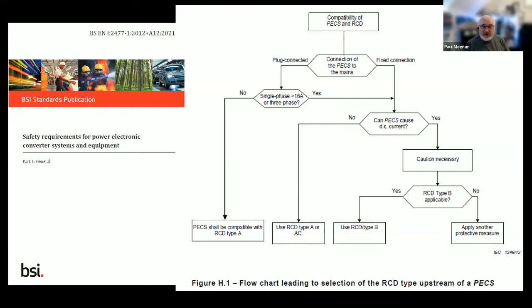We don't generally put one RCD covering everything. We used to years ago as main switches, but we realized that there was a folly in doing that, using voltage reference points. So now we've gone on a journey where we subdivided the installation, and we're now at a point where I'll show you an image where we have RCDs in each way, which gives the optimal subdivision of the installation, ensures earth leakage can't cause nuisance tripping, and if there is a fault, we minimize the impact to the user, which is what a good electrical engineer should be designing for.